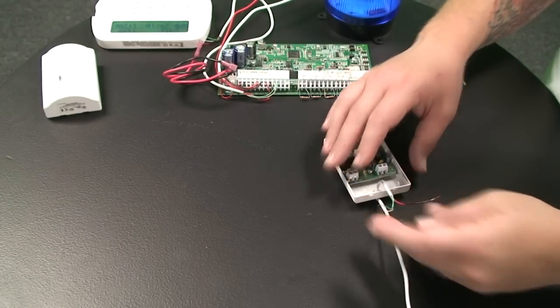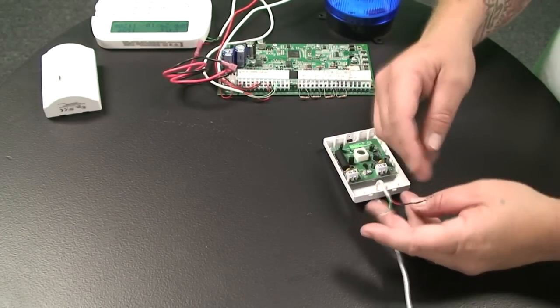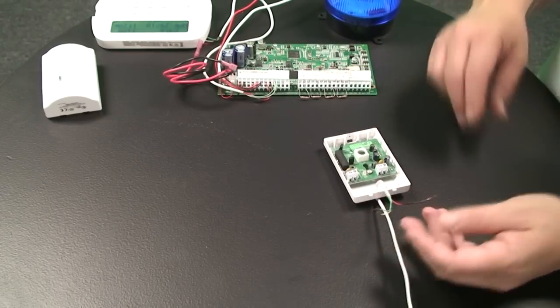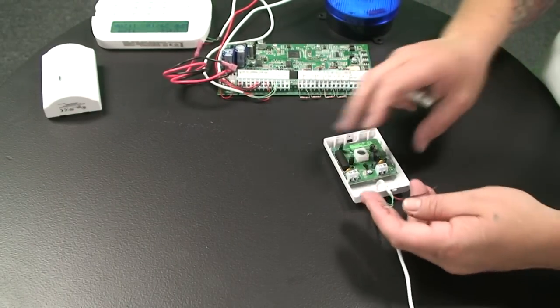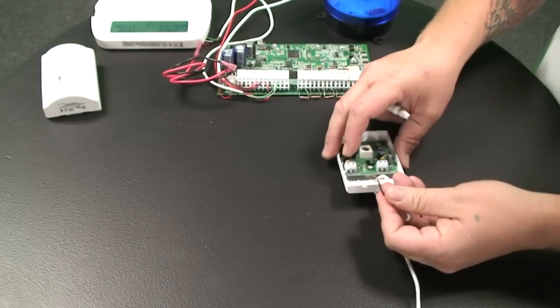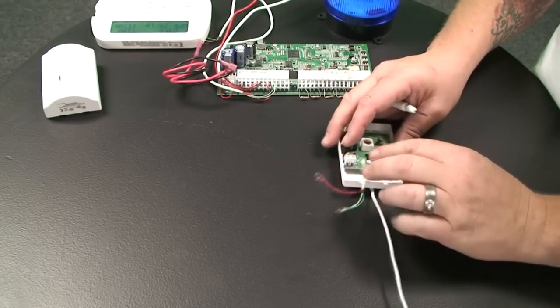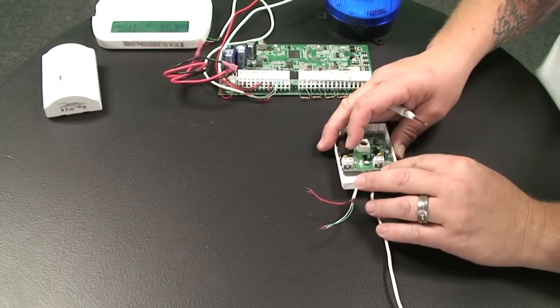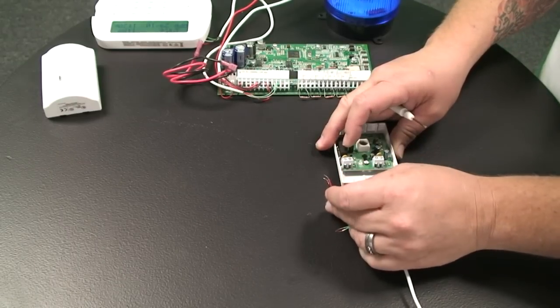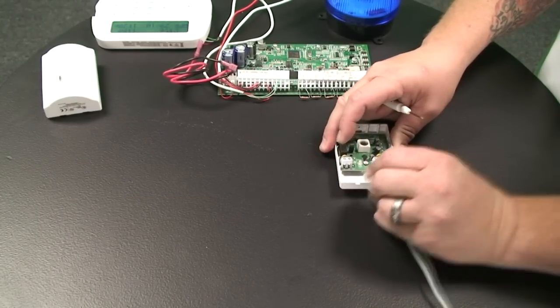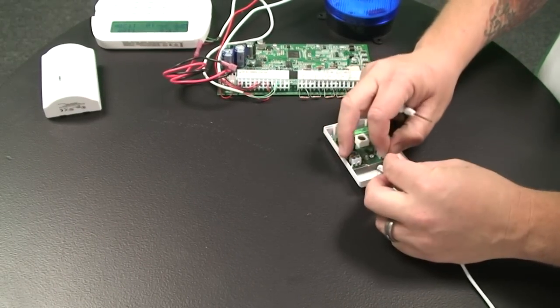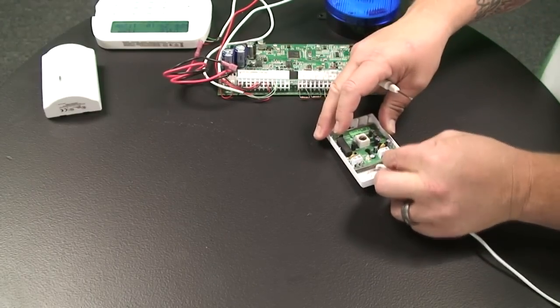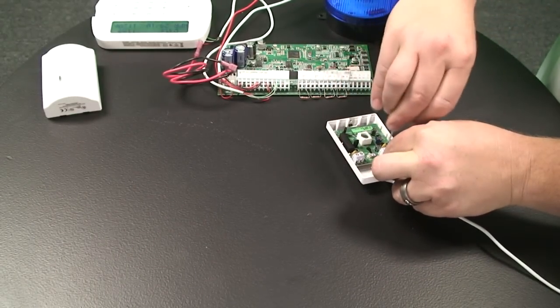So what we'll do is usually we have our four conductor: red, black, white, and green. And I like to stay with the red and the black for the power. So we'll take our red and black here. And in the motion we have a 12 volt and the ground. So I usually use a red wire as positive, so we'll go ahead and wire up our 12 volts positive into the 12 volt there.